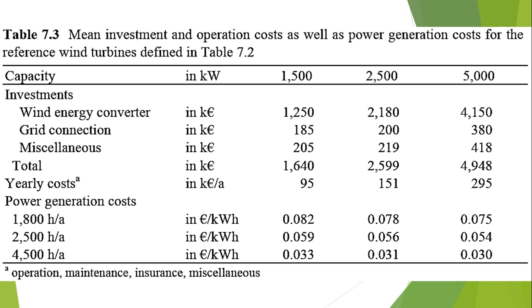Sites with 2,500 full load hours per annum are more frequently available at good locations close to coastal areas. Under these conditions, average specific power generation costs lie between €0.054 and €0.059 per kilowatt-hour. If full load hours are even lower, for example 1,800 hours per annum, electricity provision costs increase significantly. The comparison of different converter technologies with different installed capacities does not reveal any significant difference in power generation costs for the same wind speed or the same full load hours.